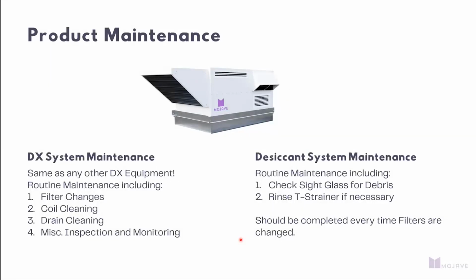Maintenance-wise, all the DX maintenance with our system is the same. Nothing's different on that front. Only maintenance on the desiccant system. There is an additional MERV8 filter protecting the regeneration tunnel. And then those T-strainers, which we've discussed in detail already. And again, from a suggested maintenance perspective, we suggest quarterly filter changes and then inspection of that T-strainer. That T-strainer really only needs to be cleaned when it has debris in it. If you're routinely servicing the unit, it would be rare that you actually need to rinse that T-strainer out unless you're in a very dusty, dirty region.